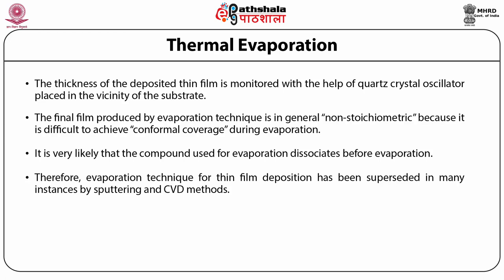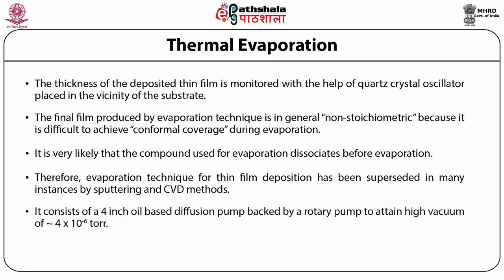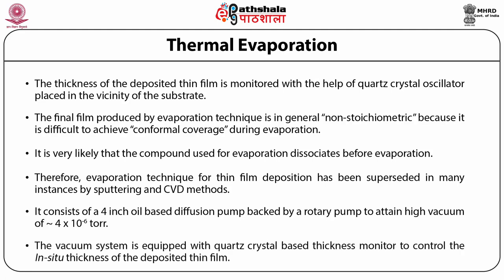A HINDIVAC thermal evaporation system consists of a 4-inch oil-based diffusion pump backed by a rotary pump to attain high vacuum of the order of 4×10⁻⁶ torr. The vacuum system is equipped with a quartz crystal based thickness monitor to control the in-situ thickness of the deposited thin film.